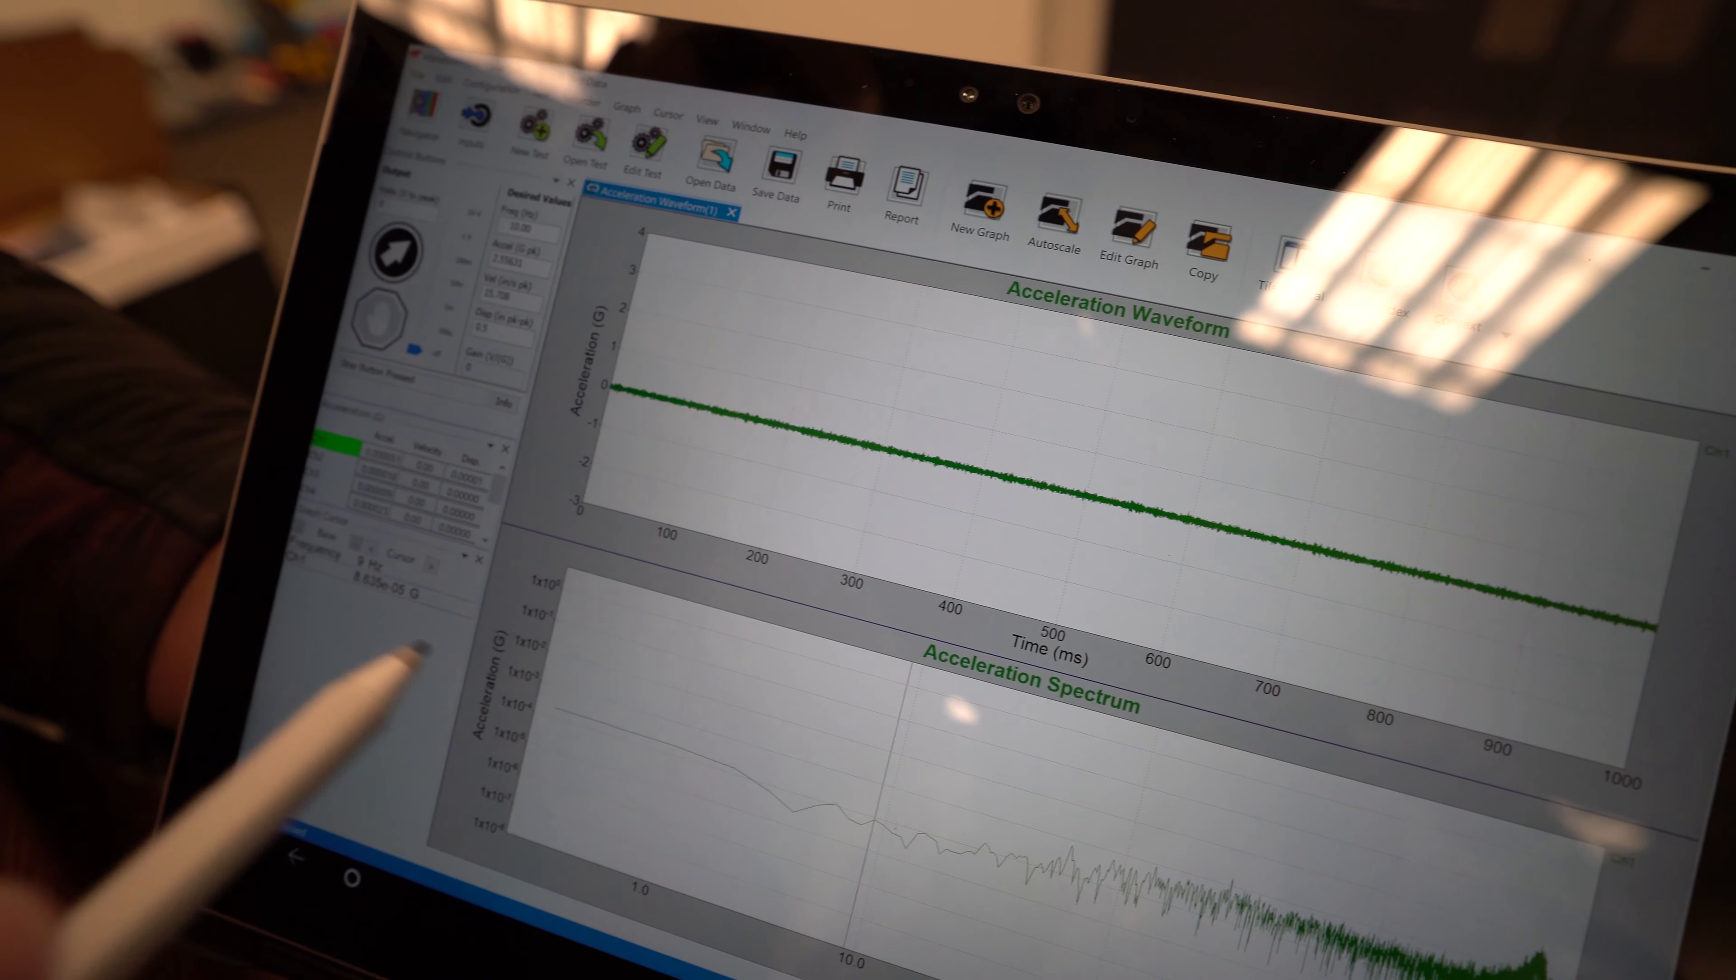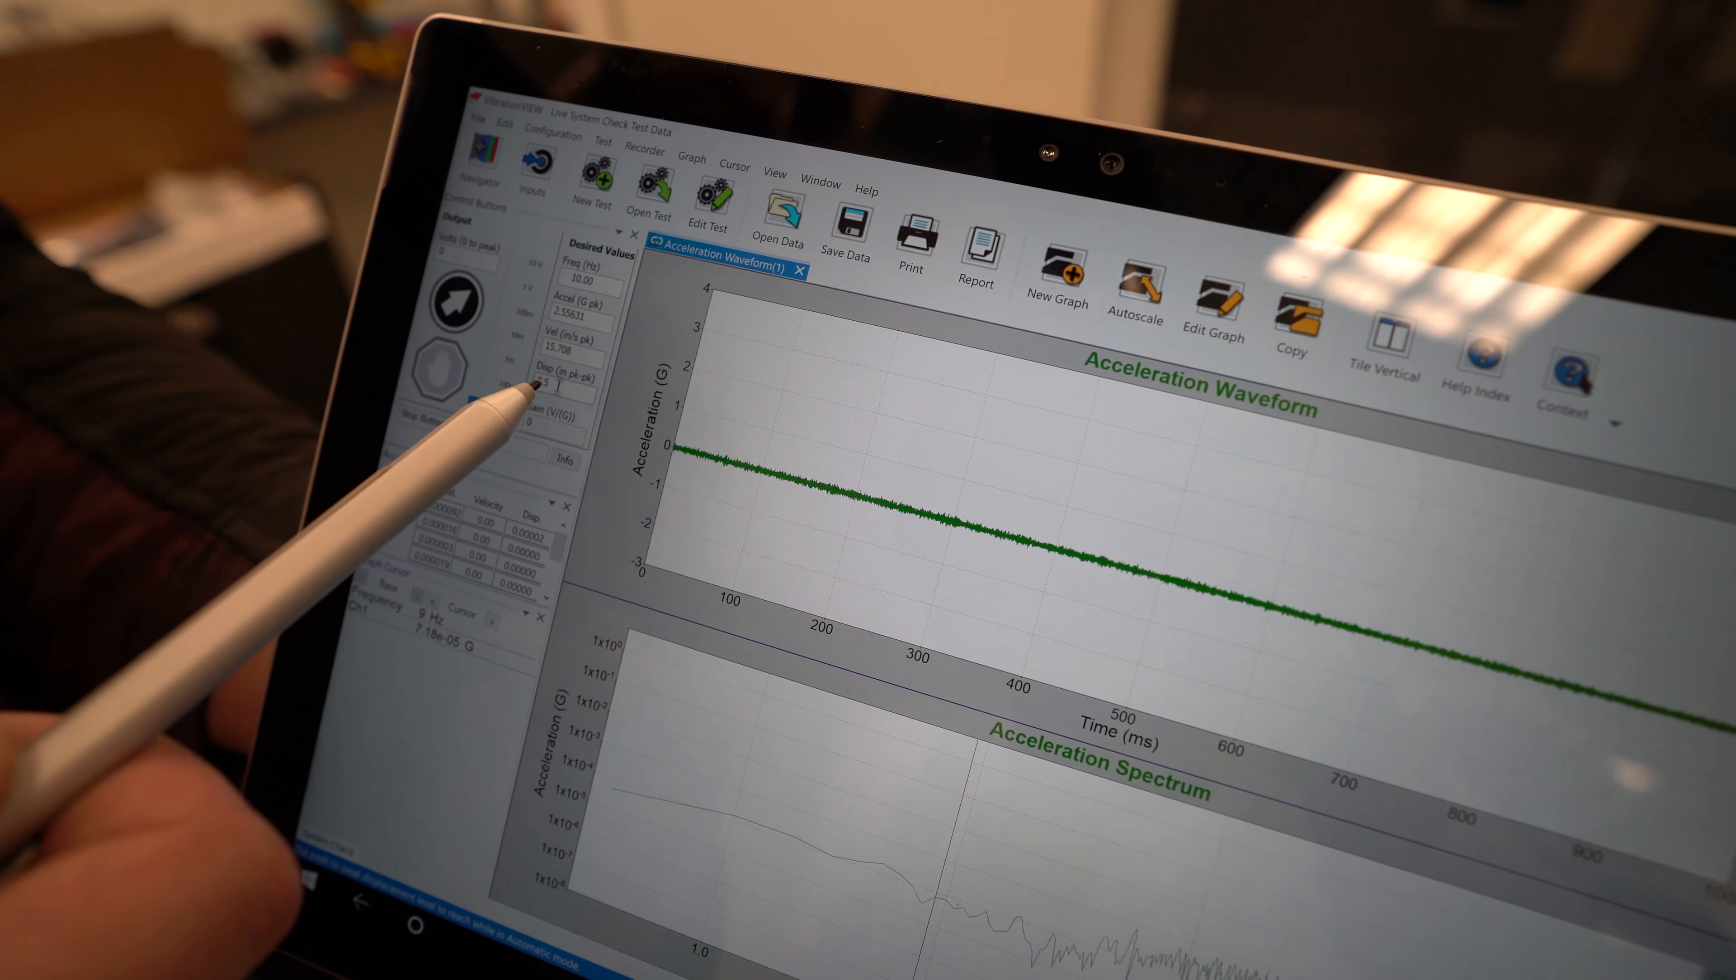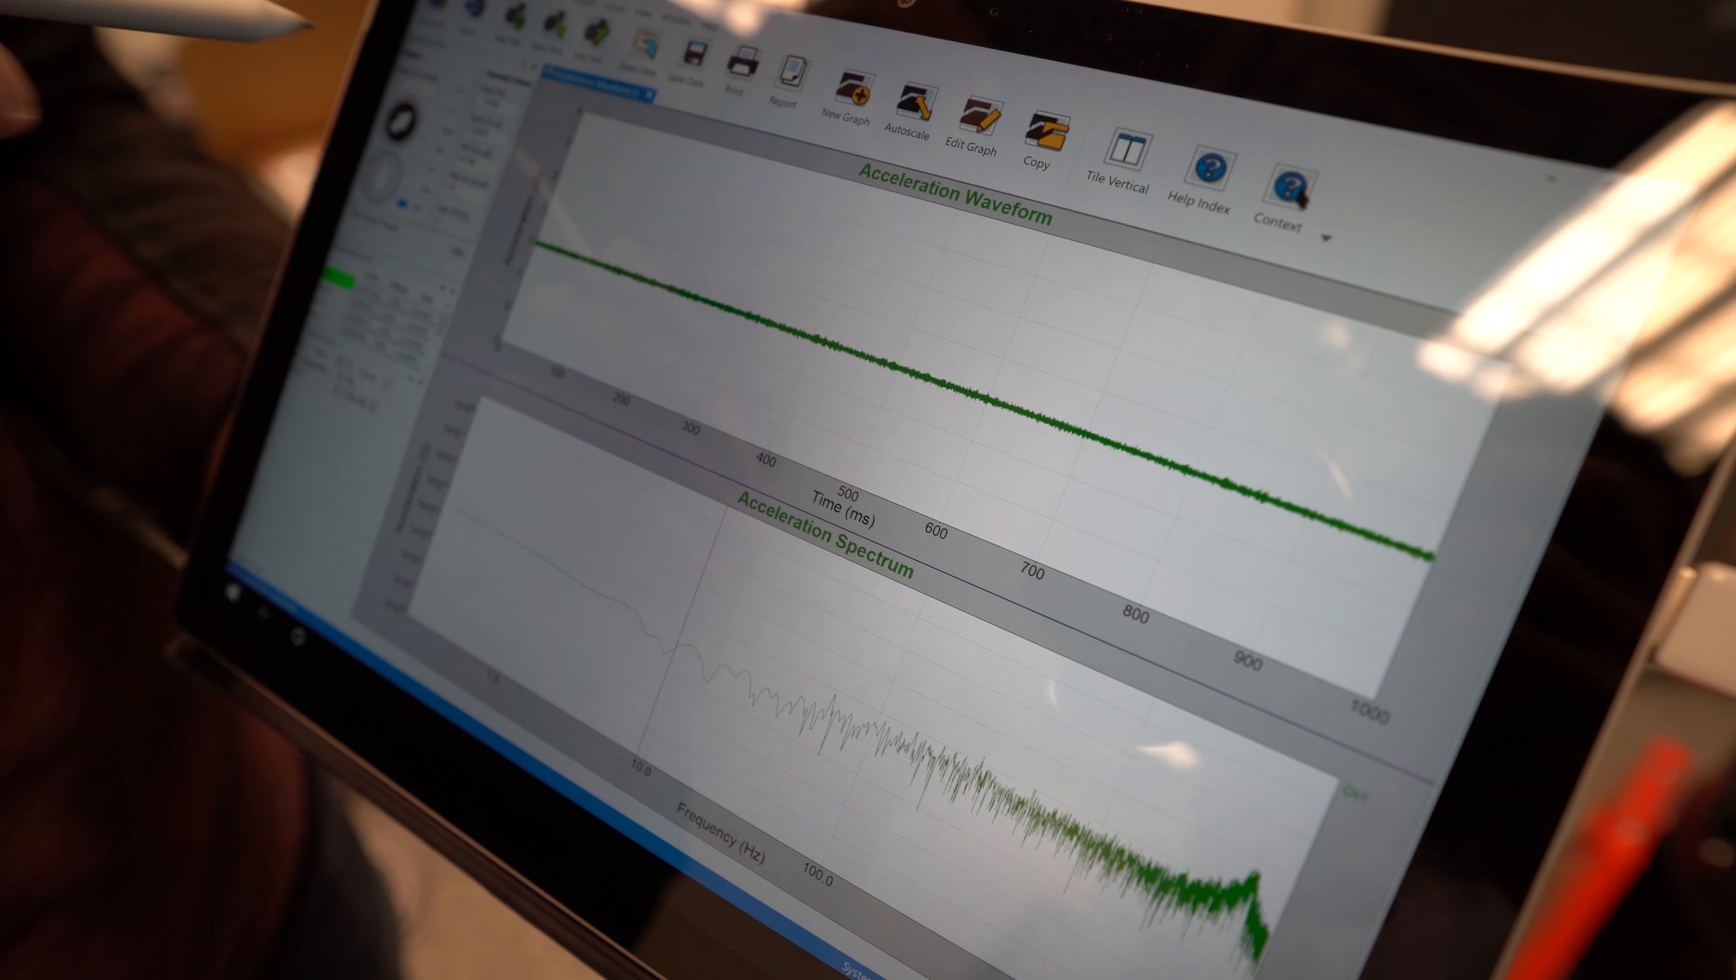Now we're in system check and we're going to go ahead and run at a frequency of 10 hertz. We're looking for a displacement of one half inch peak to peak. Let's go ahead and start that.